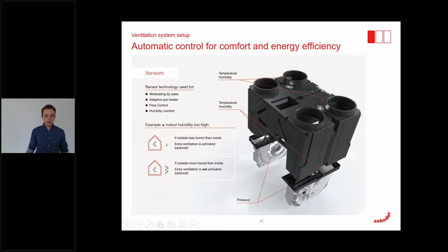If you look at the example on the left-hand side, the indoor humidity is high, and the unit detects that the outside humidity is lower. Then the unit will raise the volume flow to get the humidity out of the house. And the same applies the other way around. This also applies to temperatures. So whenever the unit detects there is a potential for cooling, for example, because the outdoor air is cooler than indoors and there's a need for cooling, the unit will increase the air volume flow to get in the coolness.